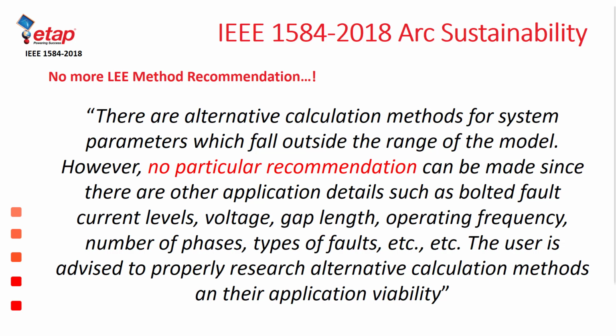This is a very important verbiage in the guideline, because it basically opens the door for any calculation method that is deemed to be accurate and applicable for applications which fall outside the range of IEEE 1584. The previous recommendation on the Lee method has brought on many consequences, including OSHA 1910.269 adding specific language about the Lee method not being suitable for the application above 15 kV.